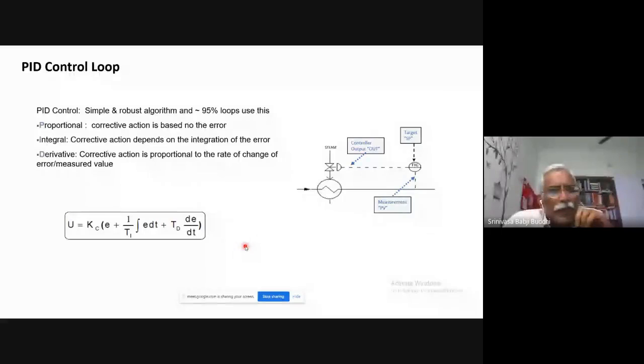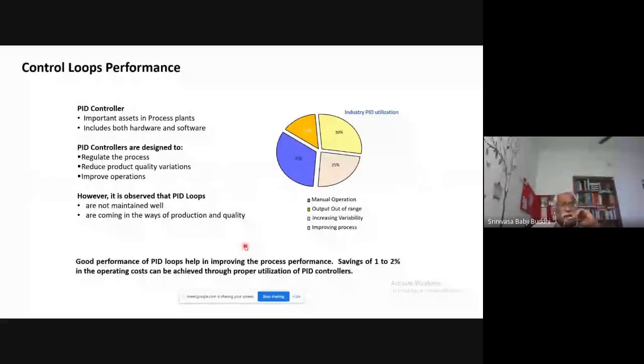Now, as I mentioned, almost 95% of the control loops in the plant use this PID controller strategy. So it is a very important asset in the plant. And as I mentioned in the previous slide, it includes both hardware and software. The hardware is the sensor and transmitter, which is installed in the field, the control valve and the actuators. So they are the hardware, and the software is the PID control algorithm that is implemented in the DCS or the PLC, in the computer control system.